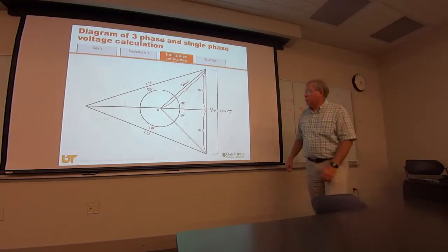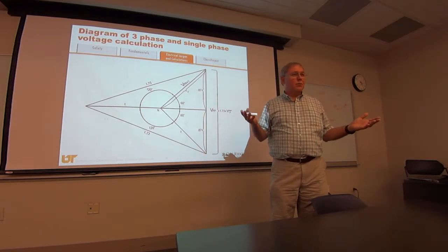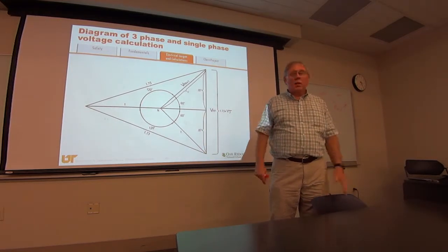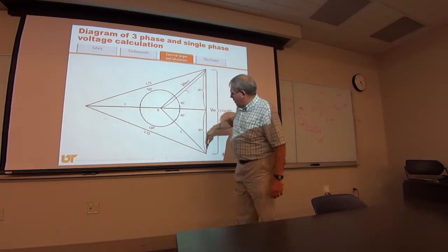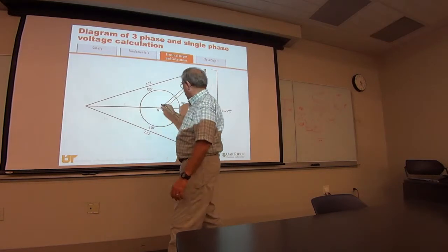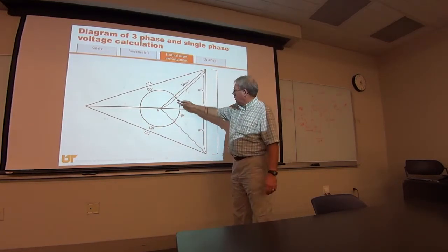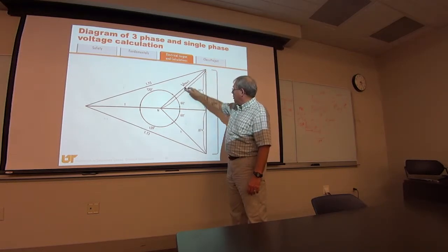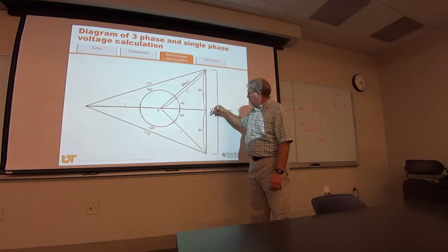Now this is interesting here. If I have a ruler and a protractor, I can do all my electrical calculations, right? Because it's all vectors and angles and stuff. So here's a delta, and here's a Y inside the delta, and the neutral is exactly in the midpoint. This is 120 degrees. So let's say I've got a voltage from phase to neutral that's equal to 1. If I do my trig, 60 degrees, this is 0.87, 0.87.